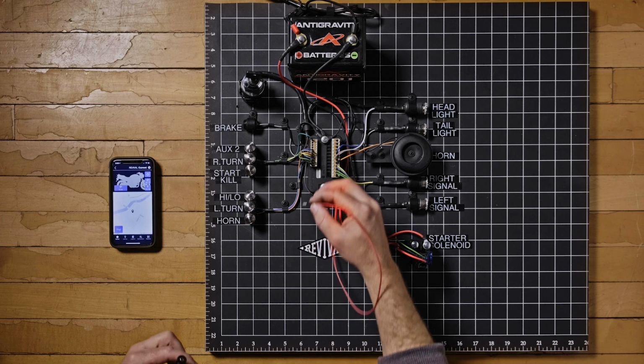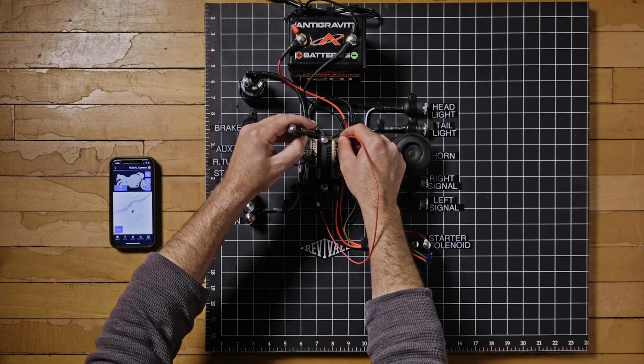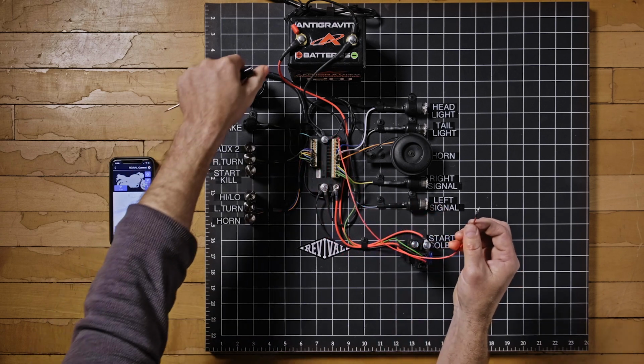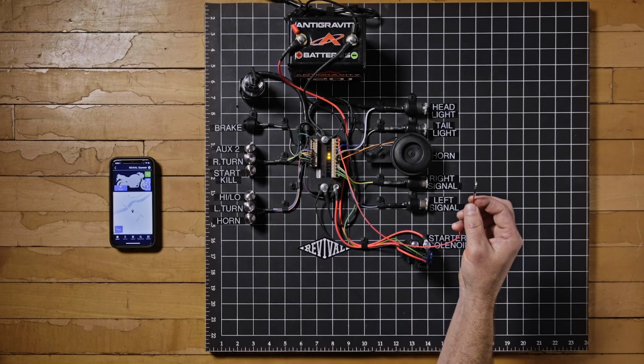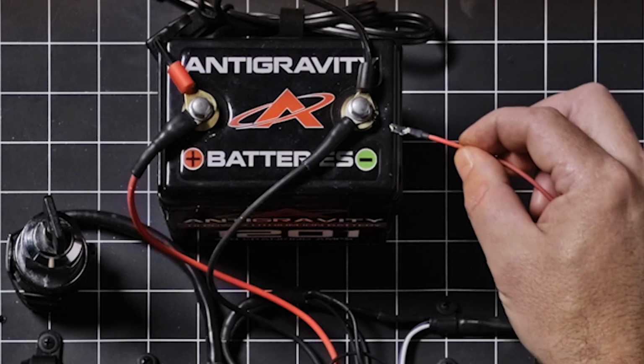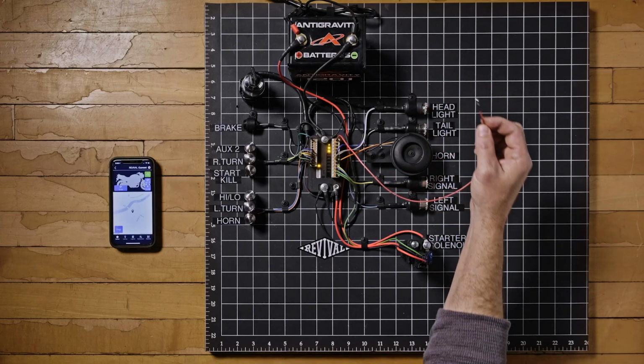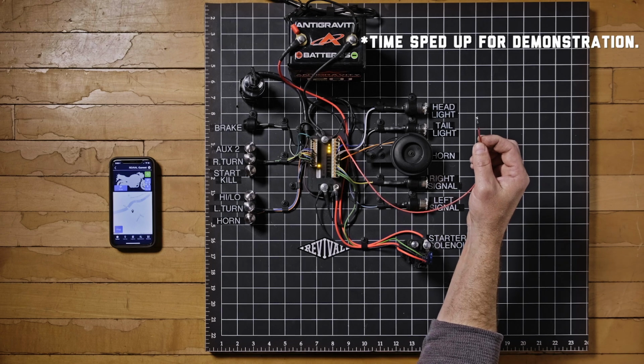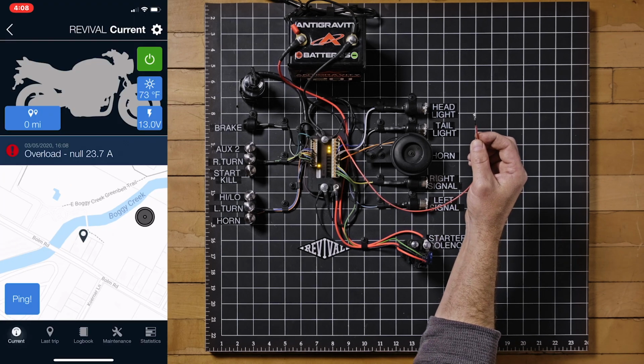Short to ground. When an electrical short is detected, the m.Unit will immediately remove power to the circuit. Approximately 15 to 20 seconds after, the terminal LED will flash and the phone will indicate a fault has been detected. Overload at output auxiliary 2.